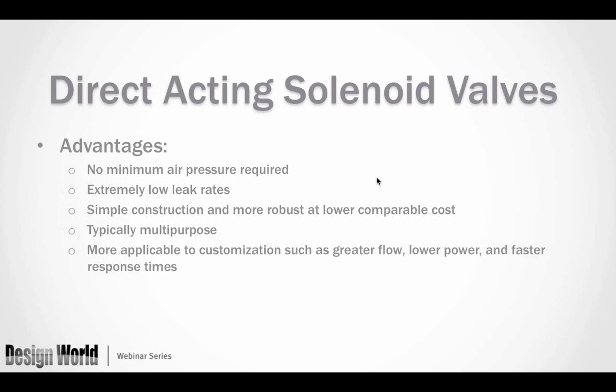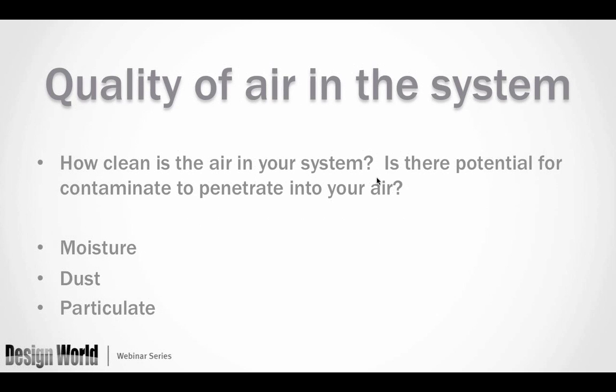Direct acting valves often feature extremely low leakage — particularly with a poppet — simple construction with no second valve on the body, and multi-purpose capability. In a three-way function you can pressurize what would normally be the exhaust port, or use it as a selector or diverter, since no internal air pressure is needed to move the spool. When properly sized and designed as a balanced valve, you still get low power consumption, and because the solenoid connects directly to the spool or poppet without double movements, you get very fast response times.